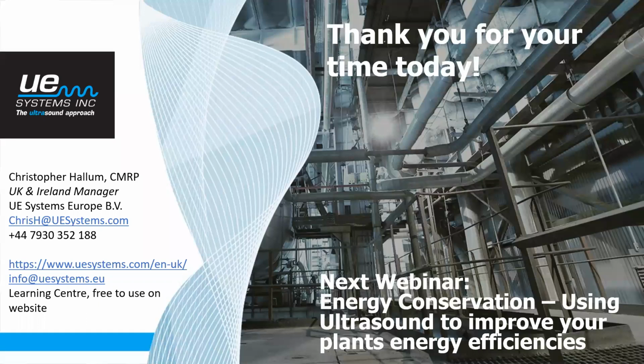So what kind of sound will there be if there is partial discharge due to harmonics by the VFD? If you're talking there about electrical fluting, we might hear not necessarily a smooth uniform sound, but a more coarse, rough sound. And if you do a sound recording, you would see harmonics relative to the electrical line frequency. For example, in most of the world you might see 50 hertz harmonics. In America, you may see 60 hertz harmonics that can identify an electrical based sound there, and you wouldn't expect to see that.